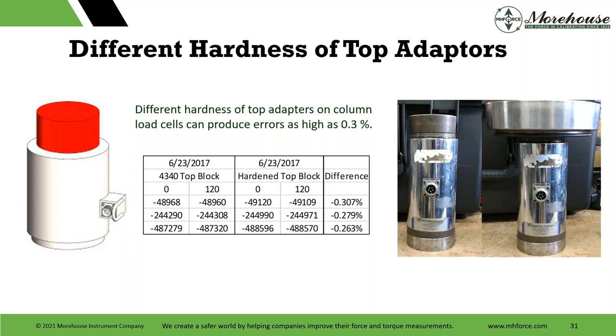I say it can produce errors as high as 0.3% because that's what we tested here. It can be much higher, it can be less. It just depends on the difference in the hardness of the top block. So with 42 to 52, you might get 0.3. If you're down at the 38s or softer, you might get higher, depending on the variability between the hardness.